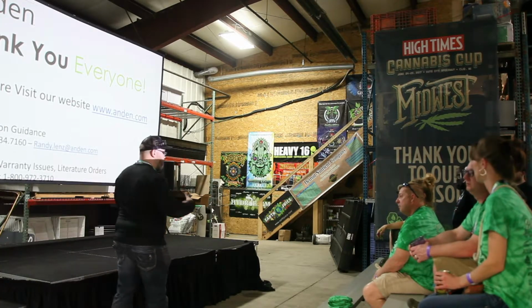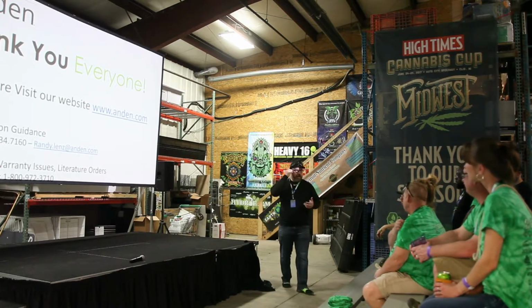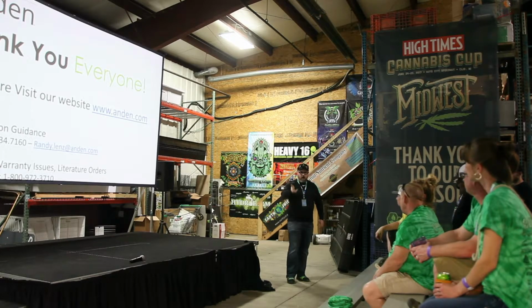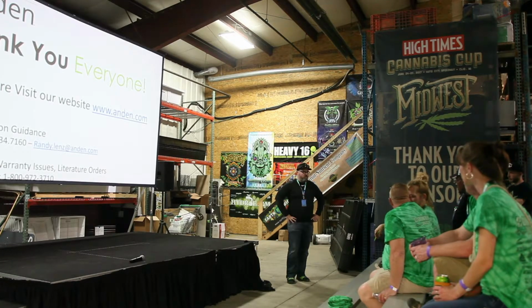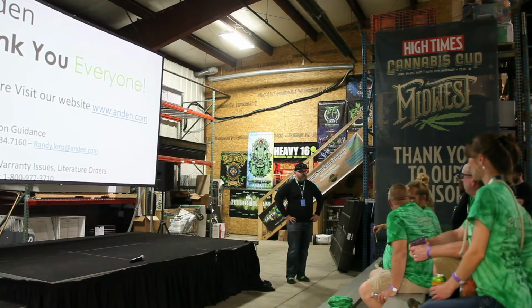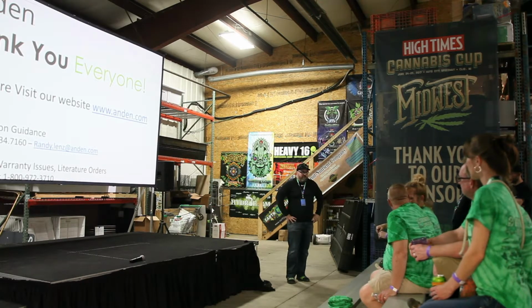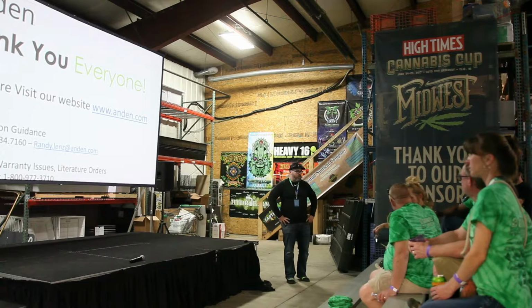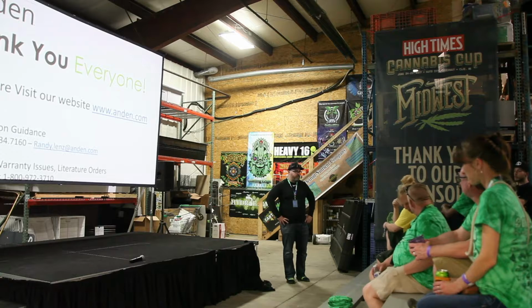So as a matter of fact, even when we size them, we always size based upon the air for multiples. So if I had a room, as an example, that needed 260 pints of removal, one of our 300-pint dehumidifiers could take care of that room, no problem. But we would quote 2 of the 200s because then if something went wrong, you're going to have that built-in redundancy. Now you could choose to buy one of the 300s, but at the end of the day, we're talking thousands of dollars worth of products, and I wouldn't risk it. And again, I'm a huge fan of multiple points of measurement.